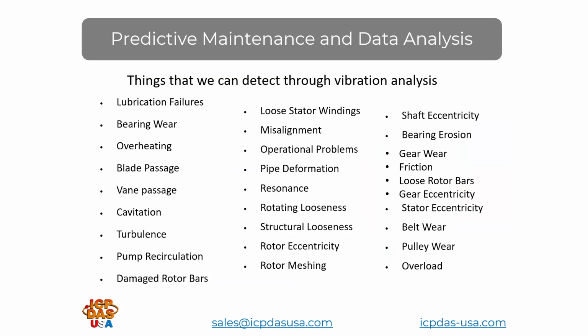Predictive maintenance and data analysis. The things that we can detect through data analysis of vibration: we can detect the unbalance of a motor, the state of its lubrication, misalignment of moving parts, cavitation, wear, bearing faults, lubrication failure, overheating, blade passage, vane passage, turbulence, pump recirculation, damaged rotor bars, loose stator windings, misalignment, operational problems, pipe deformation, resonance, rotating looseness, structural looseness, rotor eccentricity, rotor meshing, shaft eccentricity, bearing erosion, gear wear, friction, loose rotor bars, gear eccentricity, stator eccentricity, belt wear, pulley wear, overload, and more.